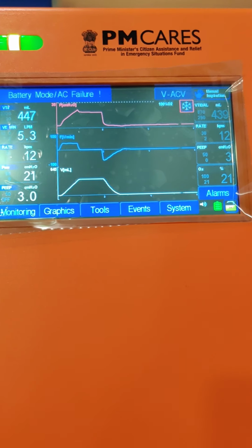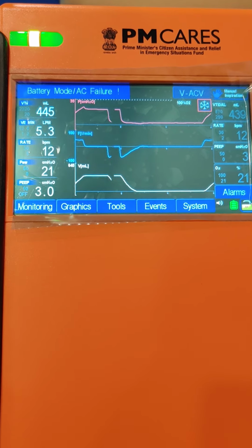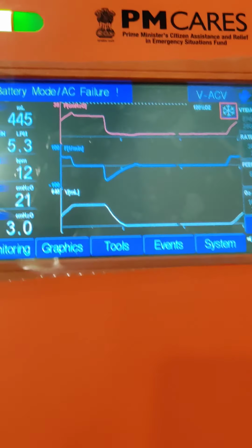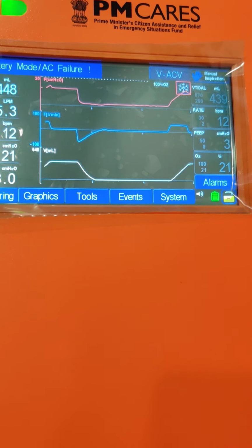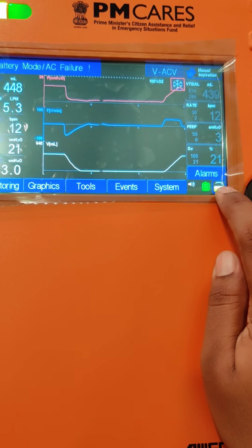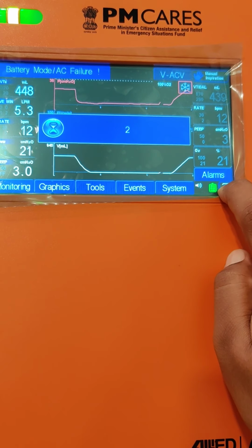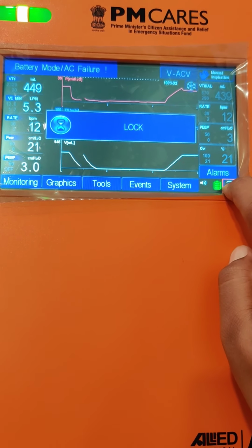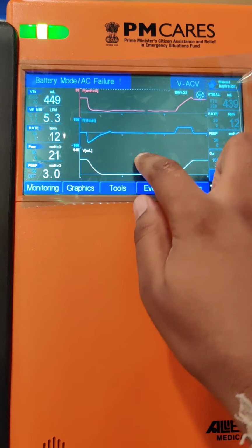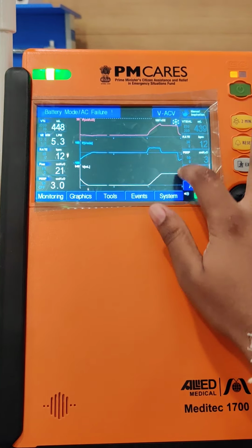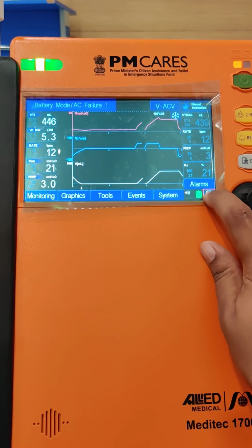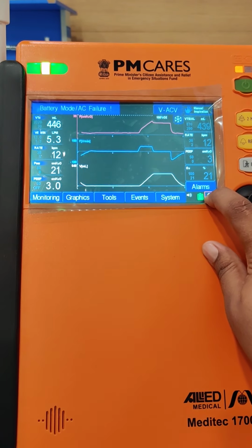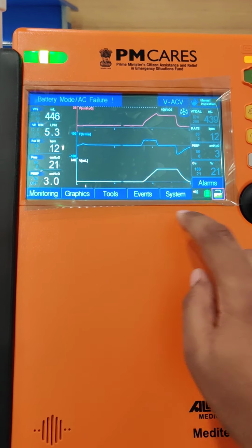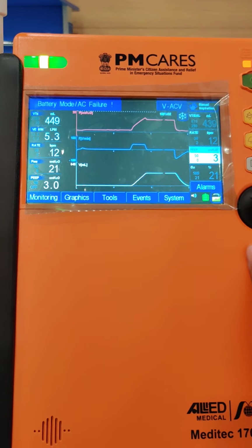This ventilator has a battery backup of 6 hours, so you can use it for 6 hours of battery operation. This over here shows the locking of the screen. If you touch and hold this, the screen will get locked, and you cannot change any of the settings. For unlocking, you again have to press and hold this. The countdown timer will start and it will show unlock. Now you can use the touchscreen as well as the knob.